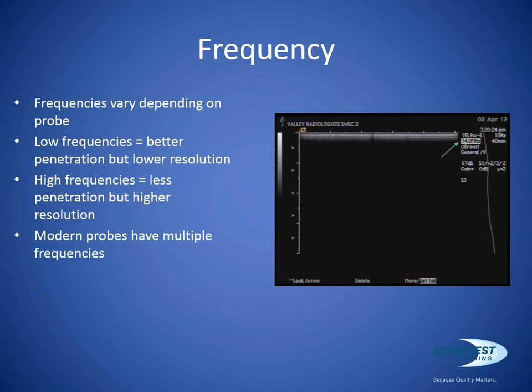On the other side of that, a high frequency is less penetration but higher resolution. This 14 megahertz that you're looking at here, if I were to scan my thyroid and only go in 4 or 5 centimeters, 14 megahertz would be practical. But at 14 megahertz, 4 or 5 centimeters is about all I can penetrate. For a deep abdomen at, say, 18 centimeters to 20 centimeters, we'd have to use 2 to 2.5 megahertz. So there's a trade-off. Modern probes do have multiple frequencies. They have primary frequencies, and they have something called harmonic frequencies, which we'll get into in a moment.